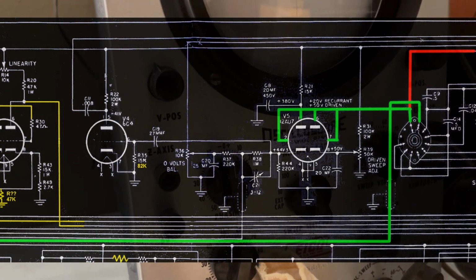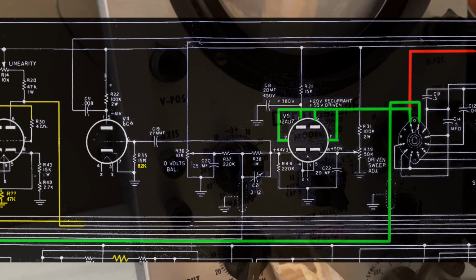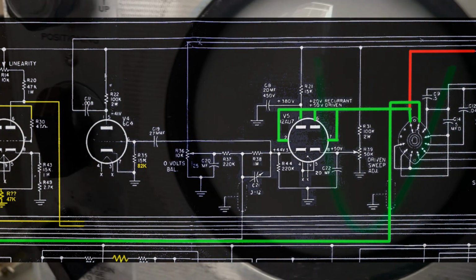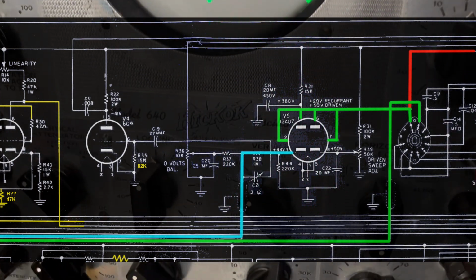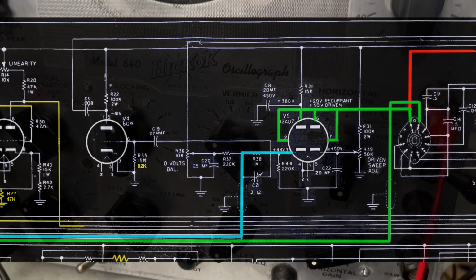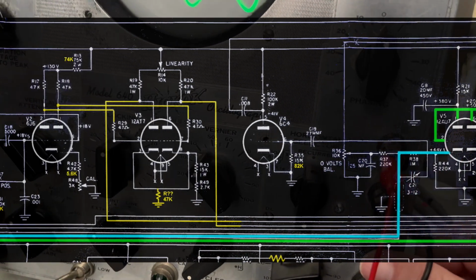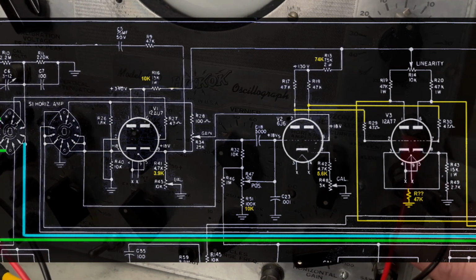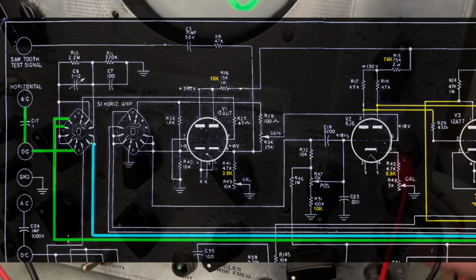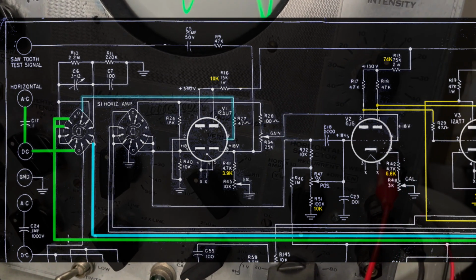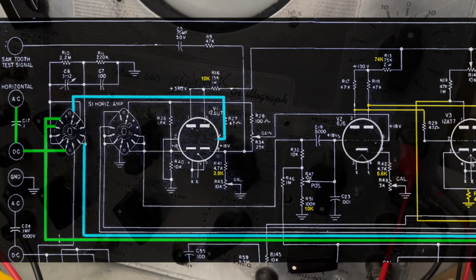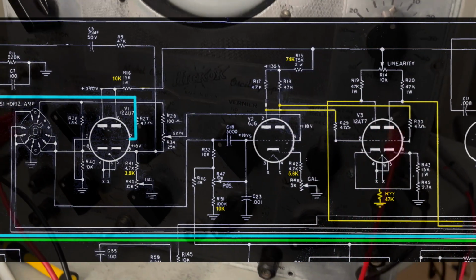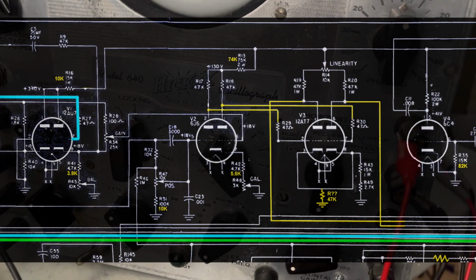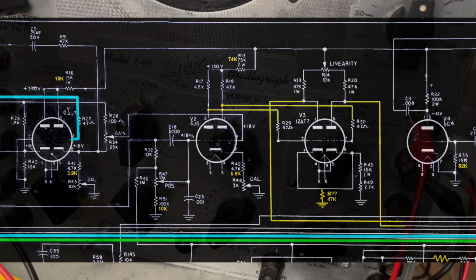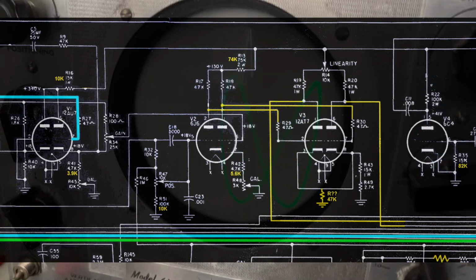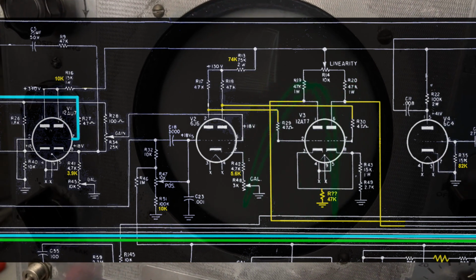As it happens, we can leverage this external cap capability to further isolate our trouble by setting the sweep selector to external cap. This should route our signal back through the same circuit employed by the sweep to effect a horizontal trace. Somehow, through the black magic of tube electronics, the signal finds its way back to the horizontal selector. And since the left half of that selector is already set to a time-based trace, so too will the other half. The signal is routed to the control grid of V1 and follows the same gauntlet all the way through the horizontal plates in the CRT. Given that this path checks out, it provides further evidence that the problem should be isolated to the sweep circuit.